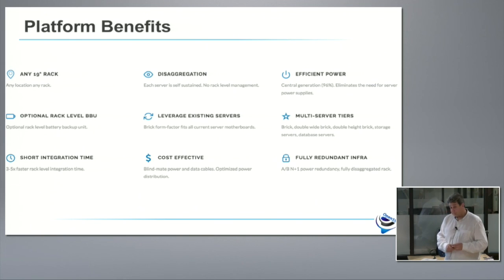The power supply in the server gets replaced by DC-to-DC converters to generate the lower voltages—that was there to start with. Before, they were doing 2 stages: high voltage to 12, then 12 to the low voltage. Now we just got rid of the high-voltage-to-12 stage. We do it in a centralized, much more efficient way. We can also do battery backup per rack, if you feel like doing that.